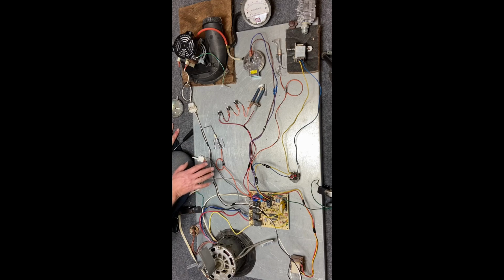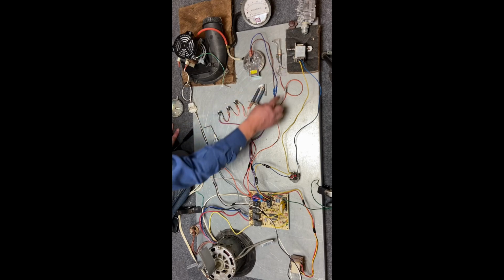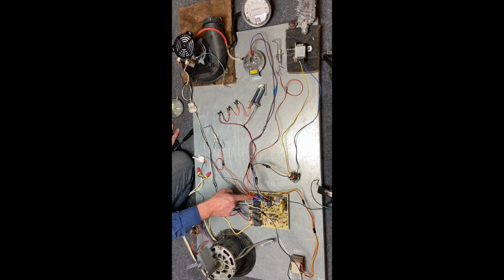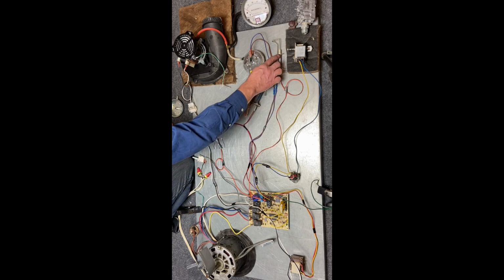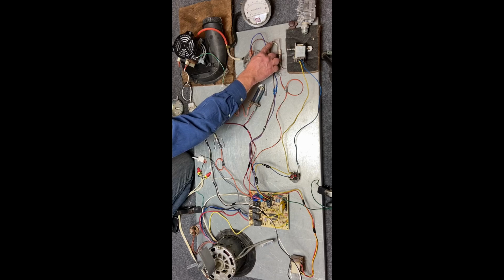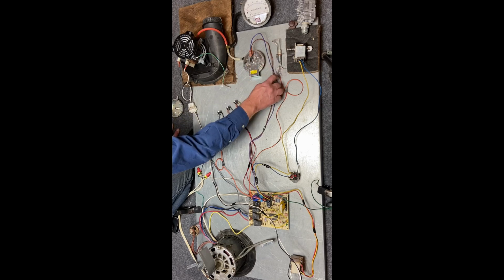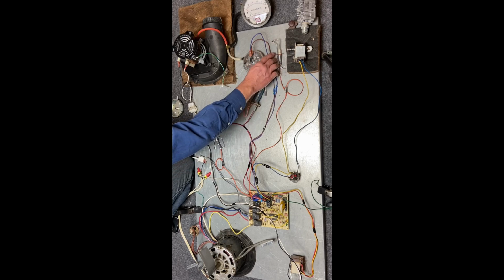Since this is a direct spark ignition unit, we also have another single wire coming from our step-up transformer. This one single wire comes over here, and it goes through this porcelain and arcs to the second terminal, which is grounded also to the board. So when we energize this, you're going to see some sparking happening right here.